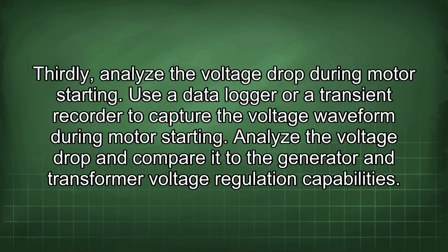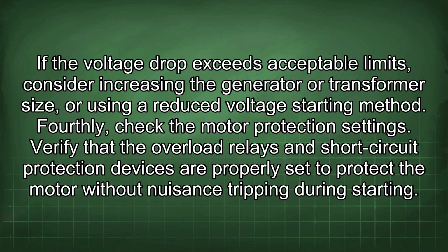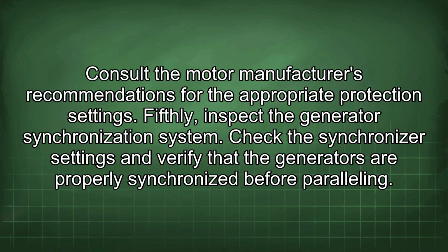Thirdly, analyze the voltage drop during motor starting. Use a data logger or a transient recorder to capture the voltage waveform during motor starting. Analyze the voltage drop and compare it to the generator and transformer voltage regulation capabilities. If the voltage drop exceeds acceptable limits, consider increasing the generator or transformer size, or using a reduced voltage starting method. Fourthly, check the motor protection settings. Verify that the overload relays and short circuit protection devices are properly set to protect the motor without nuisance tripping during starting. Consult the motor manufacturer's recommendations for the appropriate protection settings.